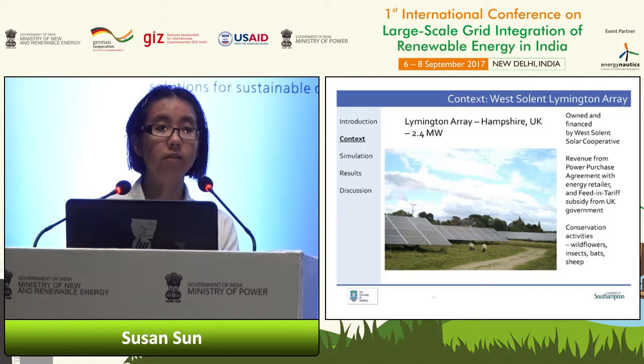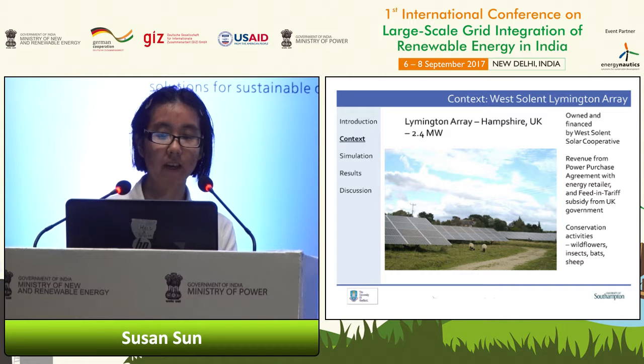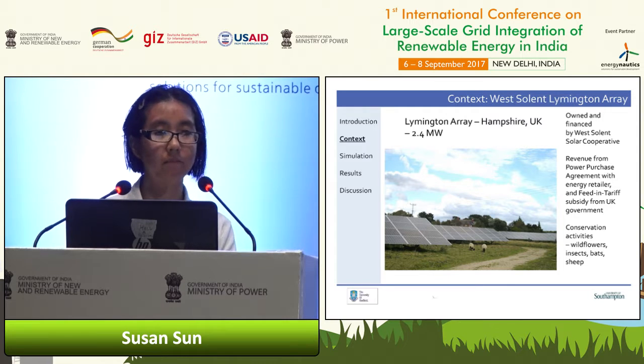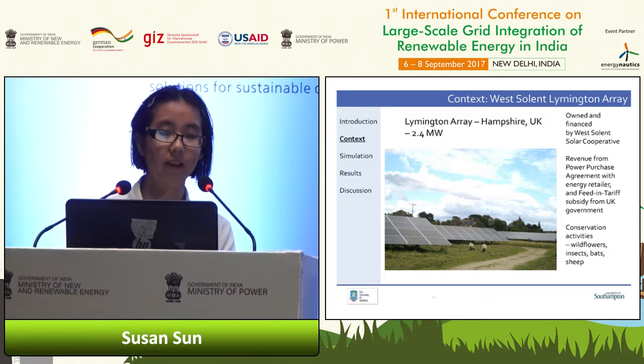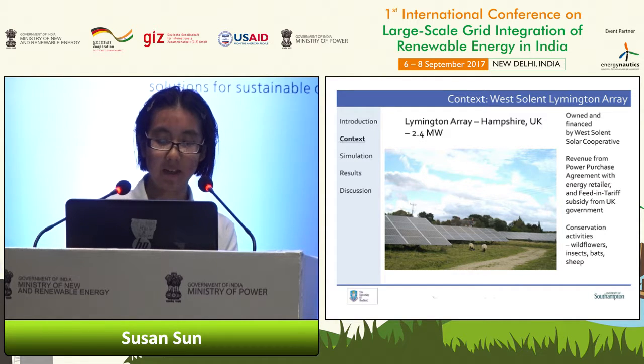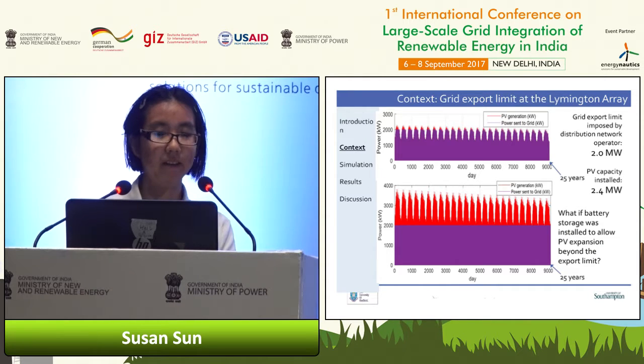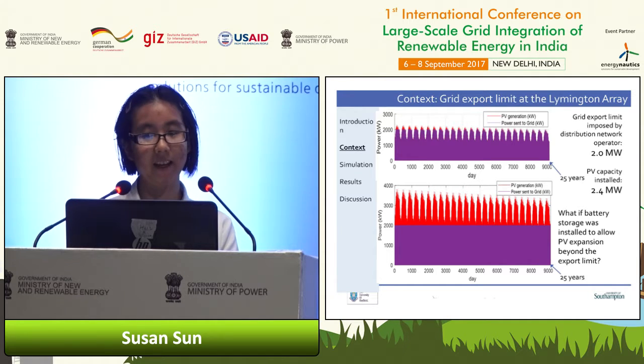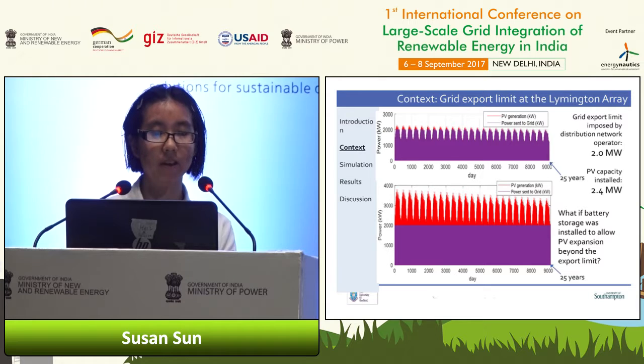So the situation being modelled is inspired by the Lymington Array in the UK. It's owned by a cooperative who collects a fixed fee per kilowatt hour from an energy retailer from this solar farm feeding power directly into the 11 kilovolt distribution network. And it's not unique at all amongst solar farms of this size in that there are constraints on the local network that mean the Lymington Array cannot export more than 2 megawatts.